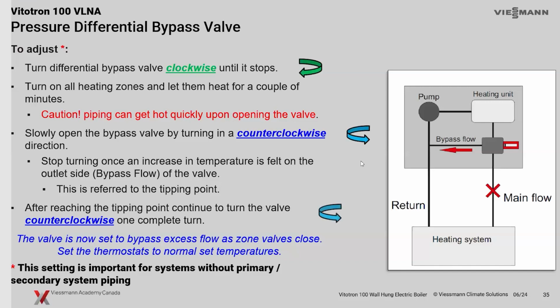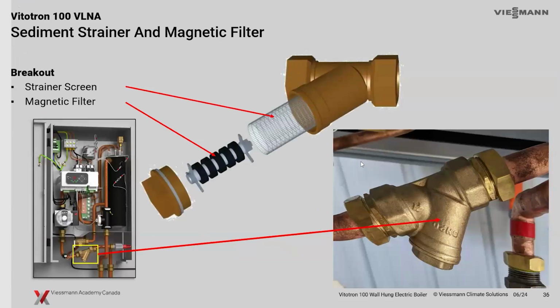All right, so that's the same stuff I just talked about, how we set that up. Also built in, we've got a little magnetic dirt filter as well. So we've got a strainer and a magnet here. That's going to pick up any debris and dirt in your system coming back. It's always advised to have these in your systems, especially if you don't know what you've got cooking inside that system, from hard water, soft water, pH levels, etc., to additives that you're adding into your systems. It's always good to have a strainer there.